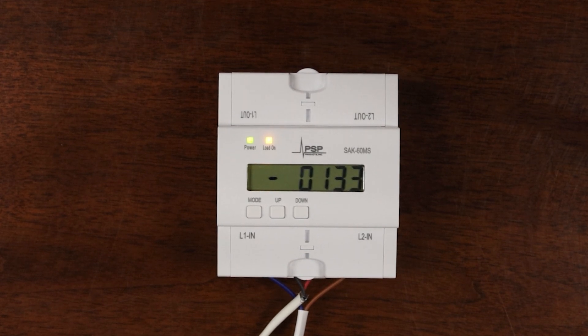So as you can see, as the load climbs, once it passes 160 amps for three seconds, then it will open to shed the load. Thusly.